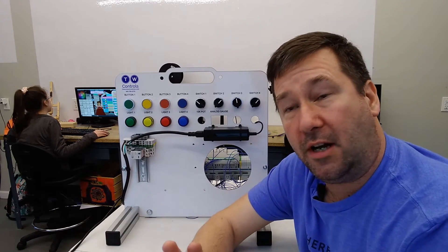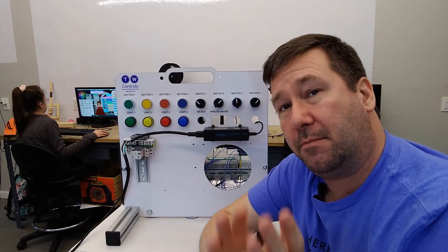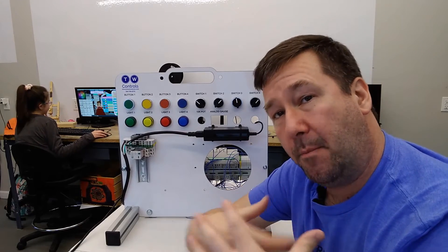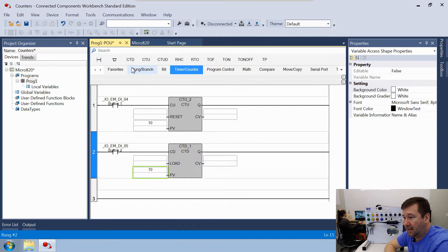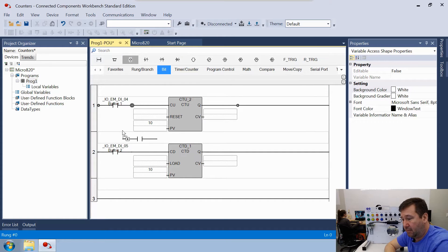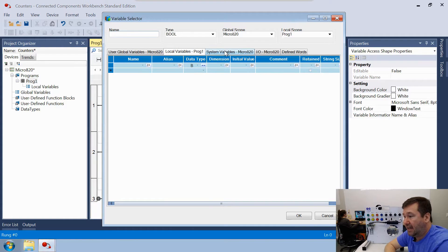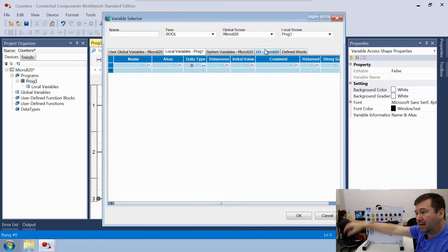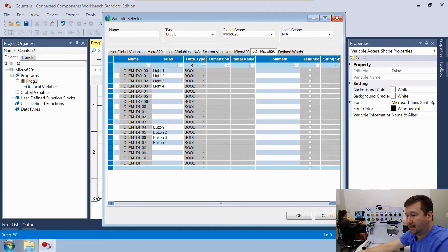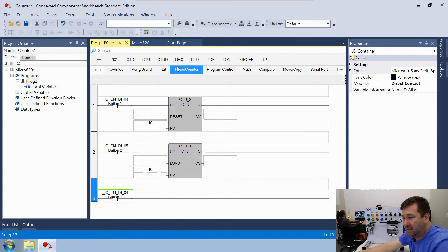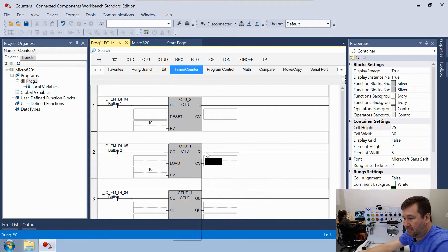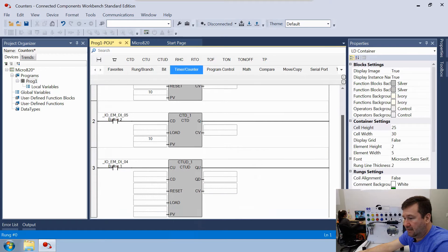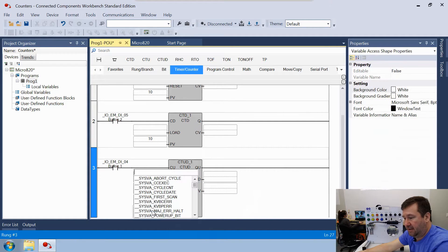Finally, there's a third type: the CTUD — count up/down counter — which combines the CTU and CTD into one instruction. Let's add another rung, go to bit instructions, bring down the direct contact, use Button 1 again, then go to the Timer/Counter tab and bring down the CTUD. Set its preset value to 10.